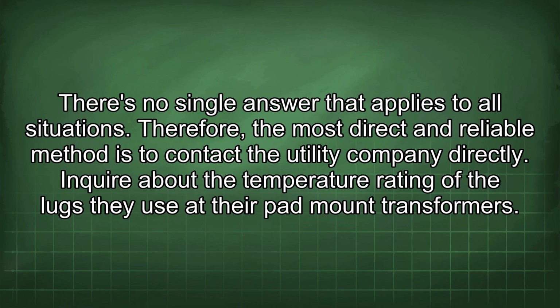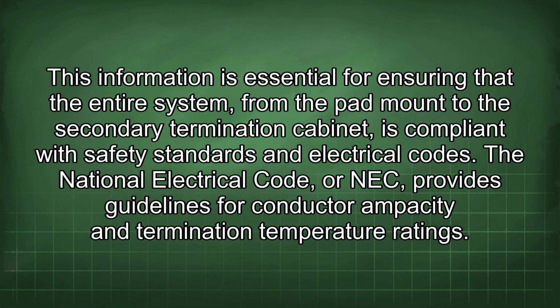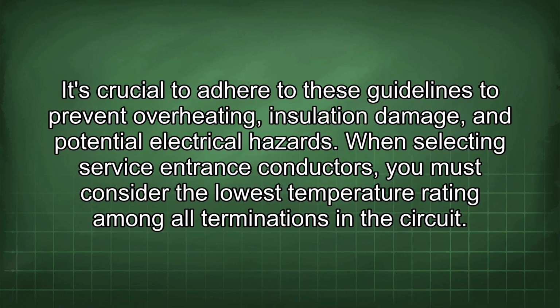Therefore, the most direct and reliable method is to contact the utility company directly. Inquire about the temperature rating of the lugs they use at their pad mount transformers. This information is essential for ensuring that the entire system, from the pad mount to the secondary termination cabinet, is compliant with safety standards and electrical codes. The National Electrical Code, or NEC, provides guidelines for conductor ampacity and termination temperature ratings. It's crucial to adhere to these guidelines to prevent overheating, insulation damage, and potential electrical hazards.